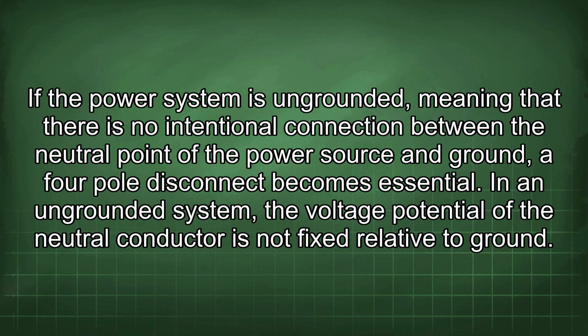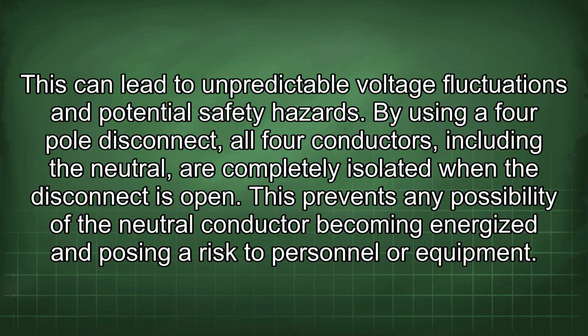In an ungrounded system, the voltage potential of the neutral conductor is not fixed relative to ground. This can lead to unpredictable voltage fluctuations and potential safety hazards. By using a 4-pole disconnect, all 4 conductors, including the neutral, are completely isolated when the disconnect is open. This prevents any possibility of the neutral conductor becoming energized and posing a risk to personnel or equipment.